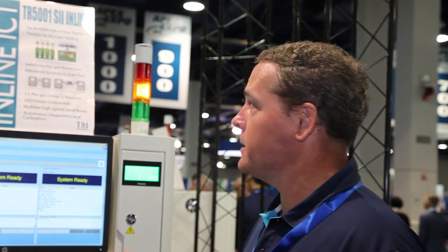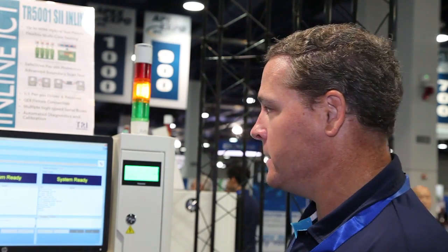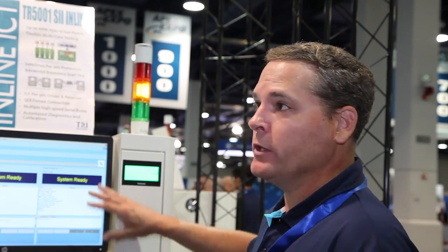What makes this machine unique is that we have the ability to have just over 4,000 hybrid test points, and we're doing something unique in the industry called multi-core testing. That gives us the ability to test up to four boards in parallel at the same time, which really cuts down on the test time and increases your throughput. This would be used in a fairly high-volume environment. The system also features a redesigned software interface to further address ease of use and programmability — something unique in the marketplace.